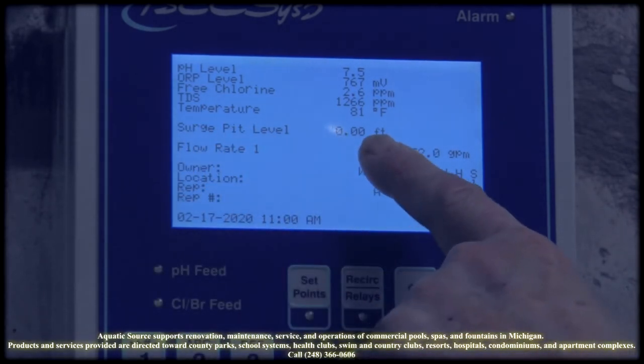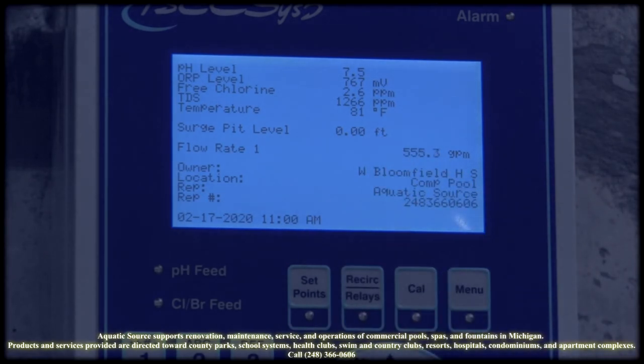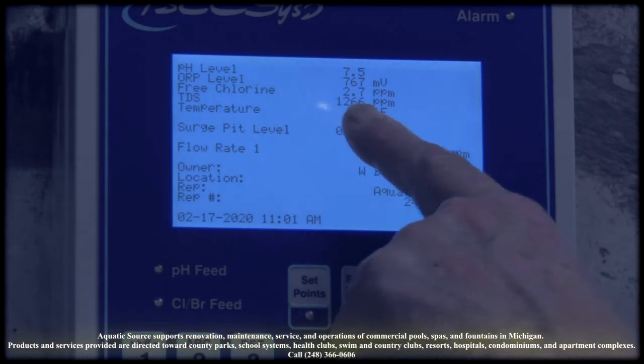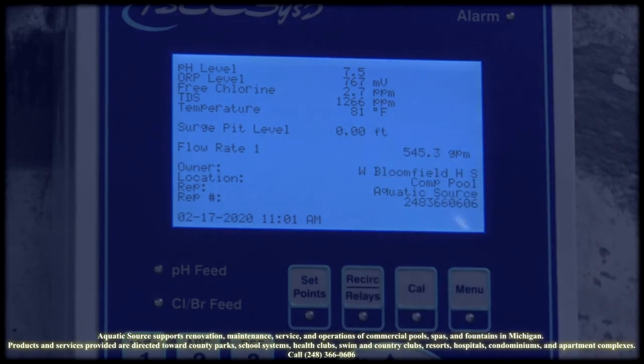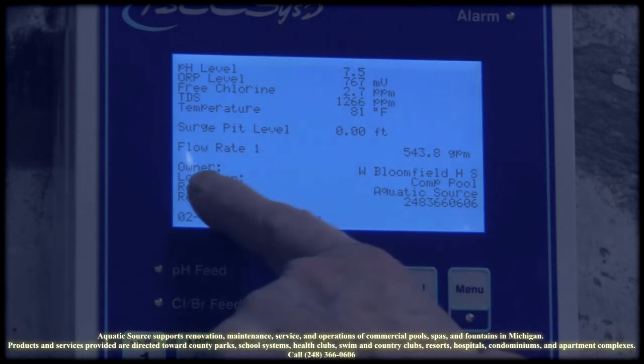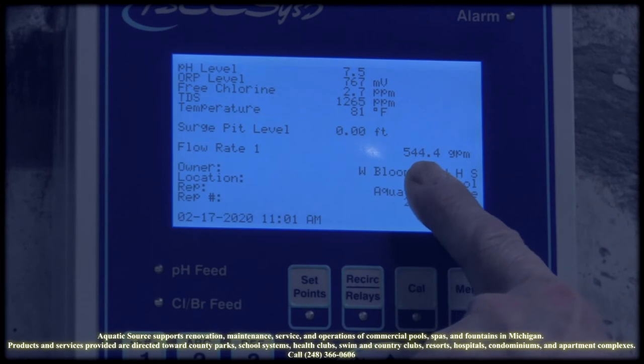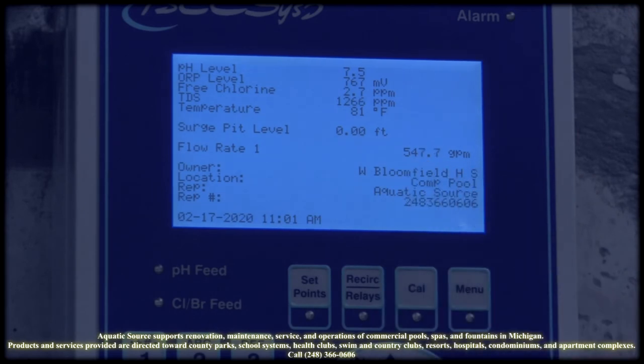We also have, on this one, a surge pit level. If the surge tank for some reason starts to overflow from a power or a pump shutdown, it will actually send an alarm through the ethernet that's in here to the operator's phone, either a text or an email. We also have the flow rate coming on. You can set that as an alarm also. If the flow rate drops too low, it'll send the operator either a text or an email. It'll also show up on their phone as an alarm.